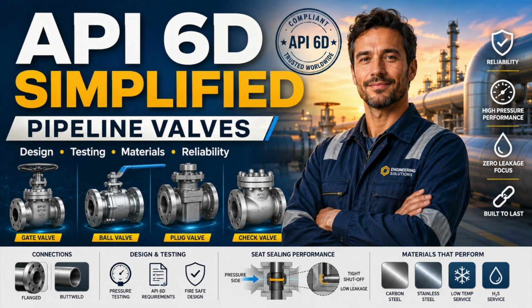The actuator and valve must be treated as one functional assembly. A correctly selected valve with an incorrectly sized actuator is an incorrectly selected valve. Actuator sizing must consider maximum differential pressure, seat friction, packing friction, bearing friction, temperature, aging, corrosion, lubricant condition, and required operating time. For pneumatic systems, use the minimum credible supply pressure. For gas over oil systems, consider the minimum available pipeline pressure. For electric actuators, consider duty cycle, speed, thermal limits, and power availability.